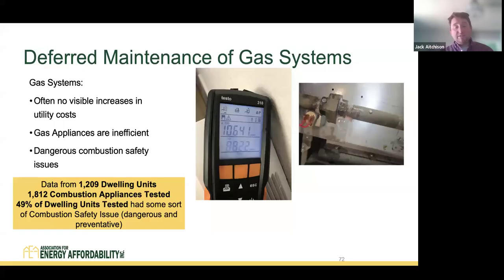And of course, we have gas leaks as well. A few years ago, we went through 1,200 dwelling units doing combustion safety testing, and tested 1,800 combustion appliances. We found that about half of them had some sort of combustion safety issue, which is a significant amount.